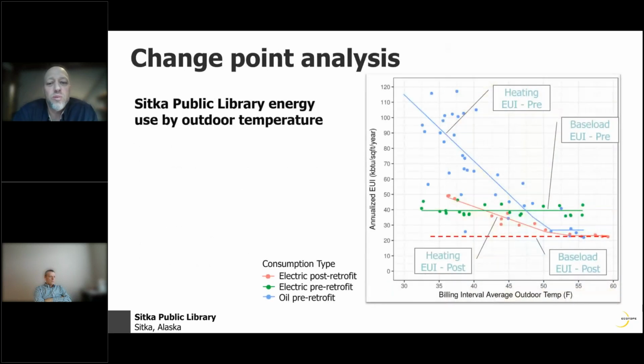This is an interesting tool we use a lot when we get into existing buildings, called change point analysis. You're essentially looking at the EUI signatures for both the heating dependent signature and the base load. The before case would be the blue and green lines. The green line across the middle is 40 EUI, representing all your base load - fans, lights, plugs. The blue line represents the temperature dependent EUI loads, which is very typical for buildings. The slope of that line tells you how efficient your building is - the lower the slope, the more efficient the building. This is a key piece when comparing high performance versus not so high performance buildings.